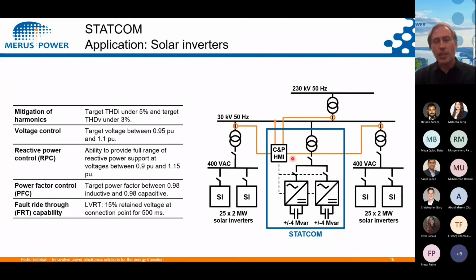In this kind of case, this is a very simple example of how a STATCOM could be connected. We connect the STATCOM through a step-up transformer to the bus bar where the solar inverters are connected. This will be located in the substation of the solar power plant, and we will have different measurements from the different parts of the installation, and also, very important, from the point of common coupling, because we need to comply with these power quality requirements and grid code requirements at the point of common coupling, where we are connecting to the main power grid, or where we are connecting to other users.